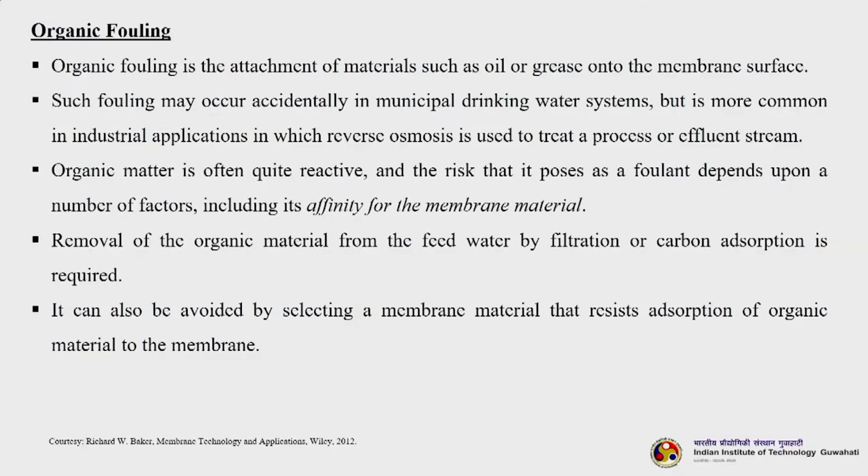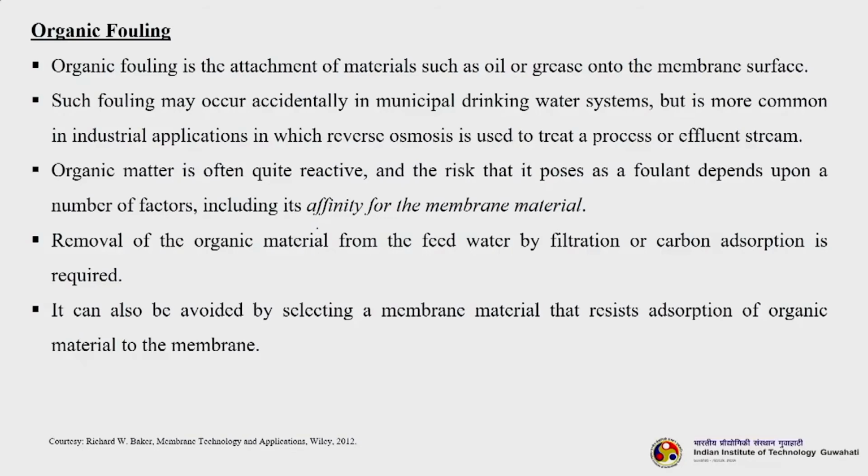such as refineries. Organic matter is often quite reactive, and the risk that it possesses as a foulant depends upon a number of factors, including its affinity for the membrane material. One of the most important things for these organic compounds is their affinity towards the membrane material. The affinity depends upon the type of membrane material and, of course, the properties of the organic compounds. Removal of the organic material from the feed water by filtration or carbon adsorption is required. It can also be avoided by selecting a membrane material that resists adsorption of organic material to the membrane.